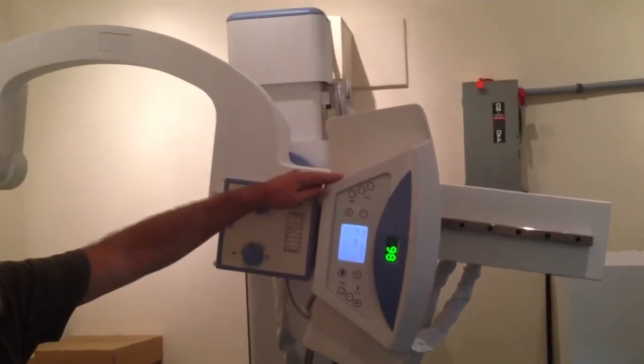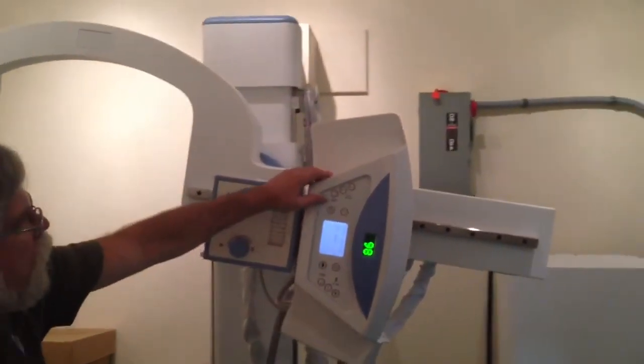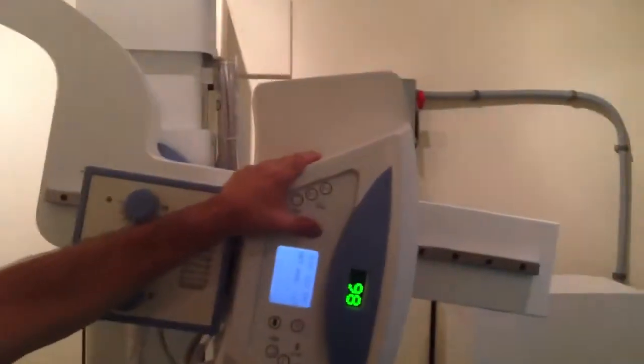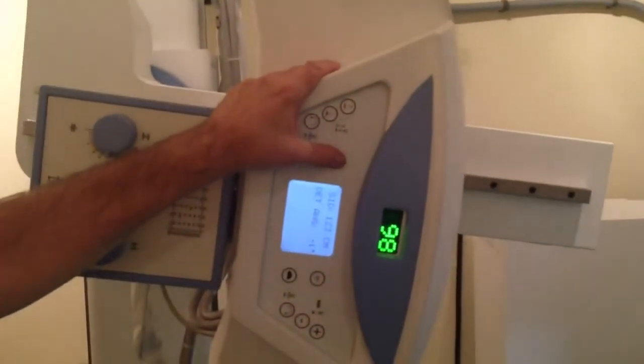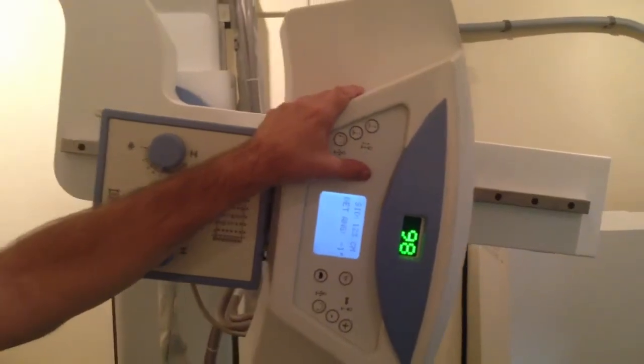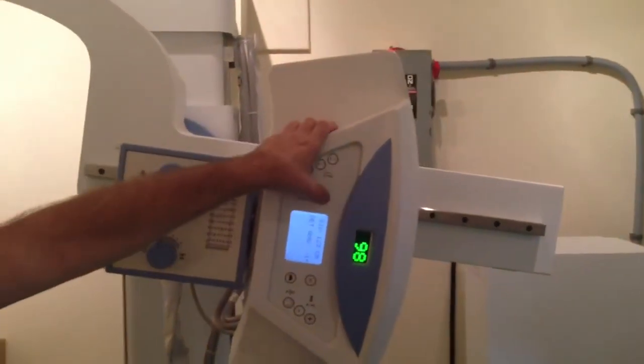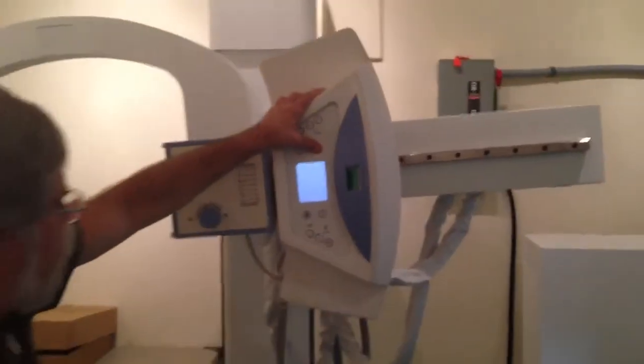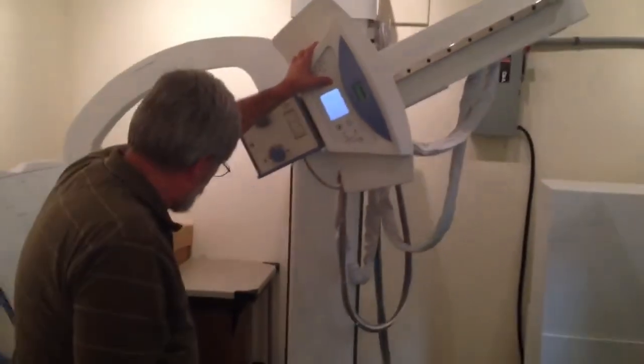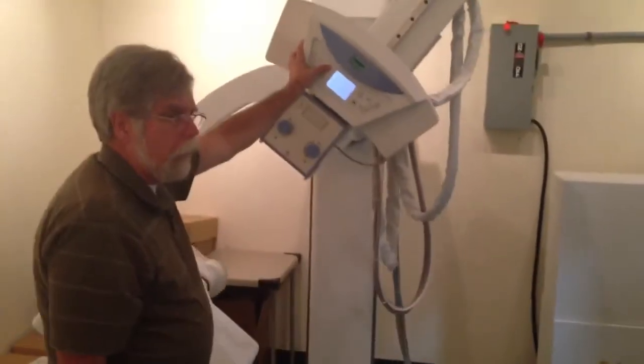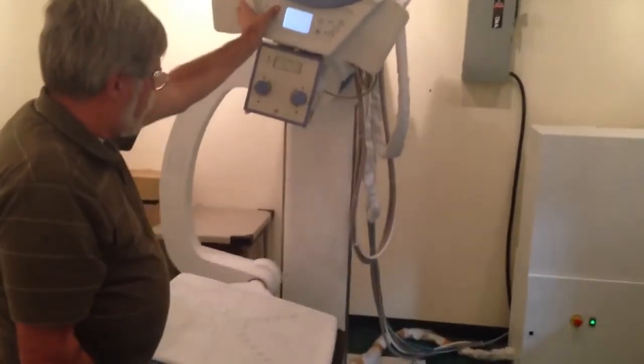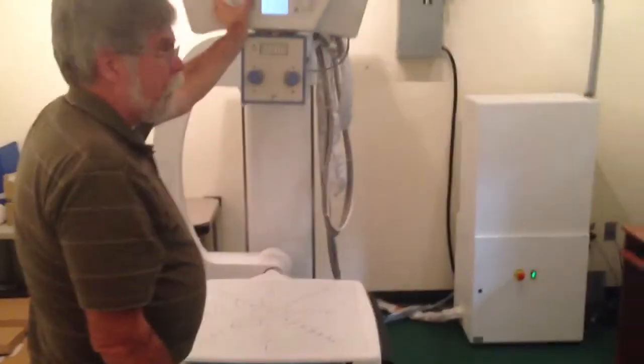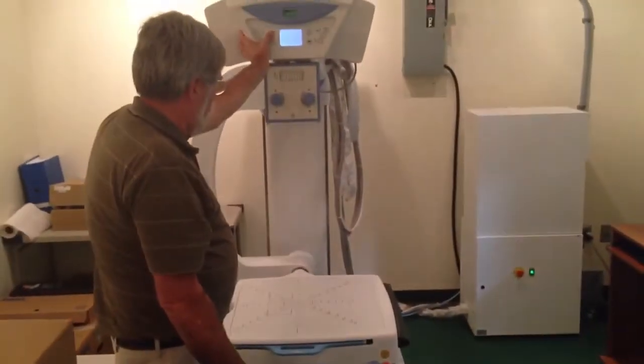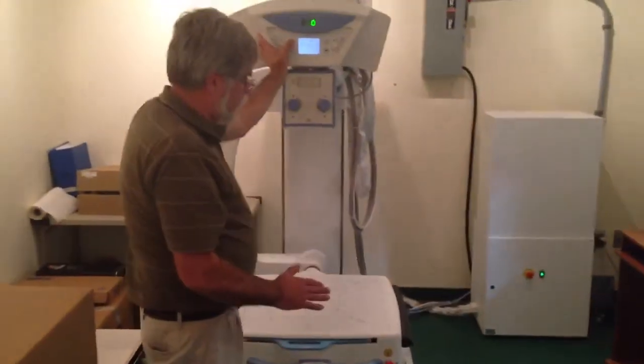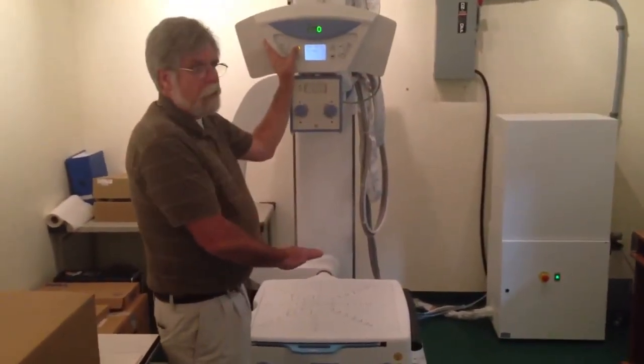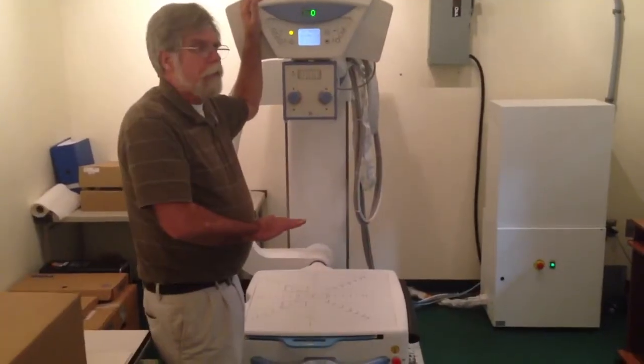It's got a couple of other nice little options on it. If I wanted to set this up to do a table shot, and this machine comes with an optional portable table that can roll into position for use of tabletop exams. If I press the tabletop button and hold it, the U-arm will move automatically into the table position for me, and then I'd be able to pull the table in, position the patient on the table, and take the exams. Through calibration, we set this up so that this automatically comes to the proper height where the table will slide right over the top of it.